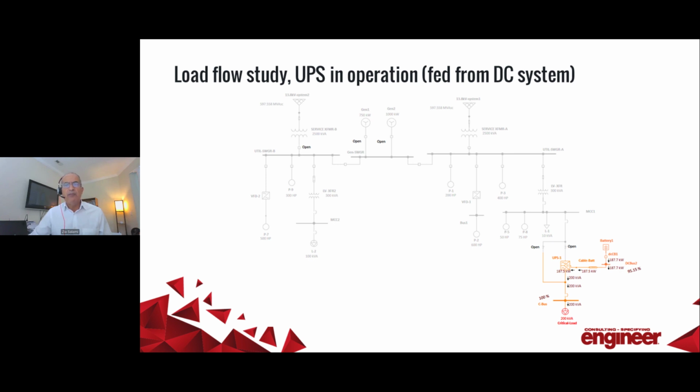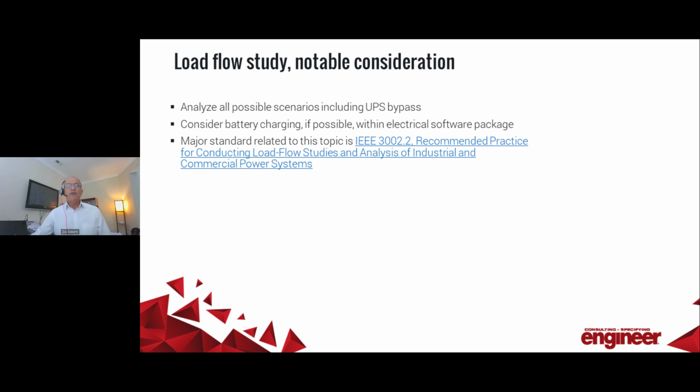And then we are able to look at the sizing for the DC system, in case it is a larger facility and your connection has the battery with a circuit breaker, the bus, and the cable. Therefore, you are able to size the DC system. Now, just some notable considerations I want to point out: we always need to analyze all possible scenarios when dealing with the UPS system.